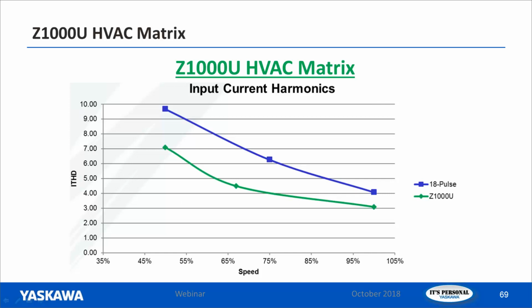One common level that's referred to a lot, you see it in a lot of specifications, is 5%. We want to be under 5% total harmonic distortion or current distortion. Well, with the multi-pulse, 18 pulse, for instance, we've got to be up to 90% speed before we're really achieving that 5% or less harmonic distortion. But with the Z1000U, we can be as low as 65% speed and get below that 5% threshold for harmonic distortion.